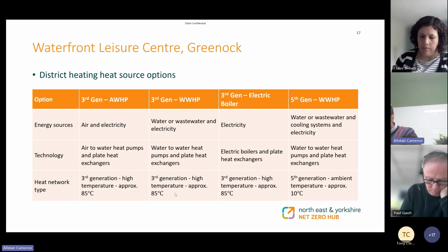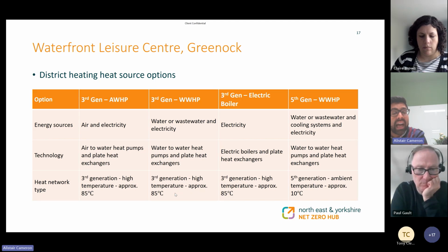So with all options, there's various types of district heating that we felt would be applicable and viable for the development, and we looked at various options, and some of these are tabled on this slide. So the first option, which would be the air source heat pump using air and electricity as an energy source, and that would essentially provide high-grade heat to each of the buildings, and then you transfer that heat into the building via a plate heat exchanger.